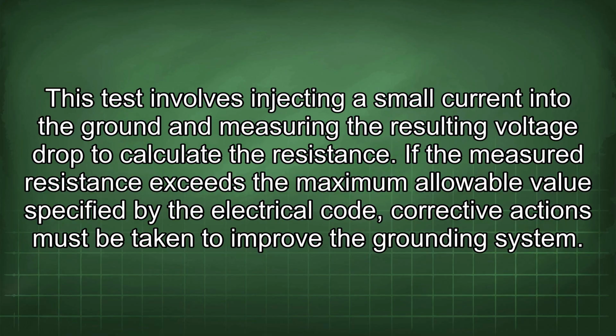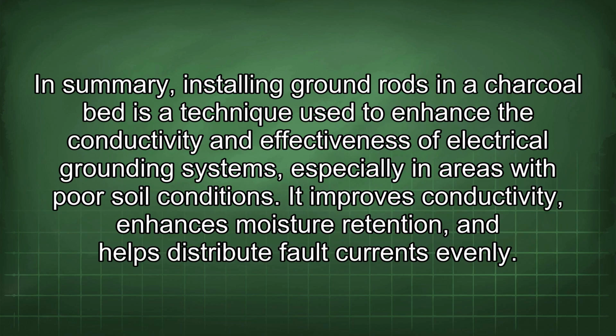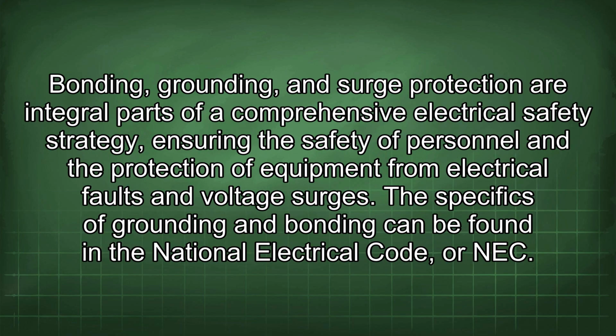In summary, installing ground rods in a charcoal bed is a technique used to enhance the conductivity and effectiveness of electrical grounding systems, especially in areas with poor soil conditions. It improves conductivity, enhances moisture retention, and helps distribute fault currents evenly. Bonding, grounding, and surge protection are integral parts of a comprehensive electrical safety strategy, ensuring the safety of personnel and the protection of equipment from electrical faults and voltage surges.